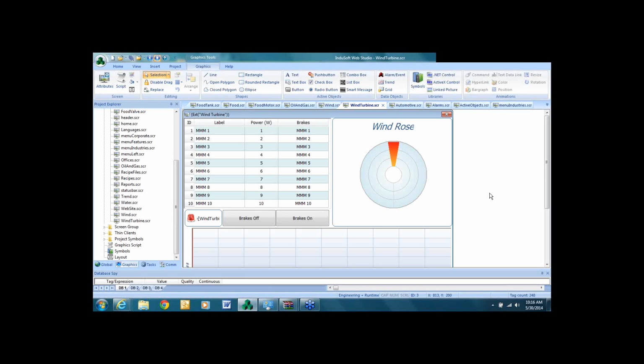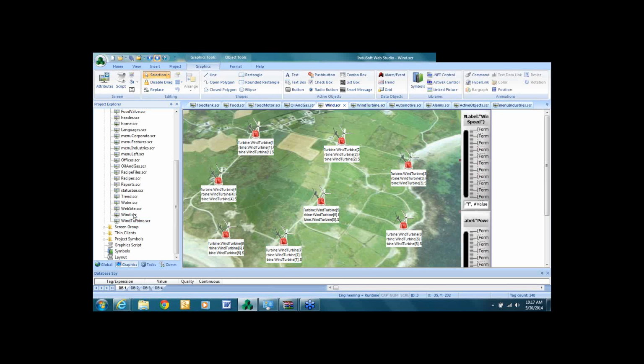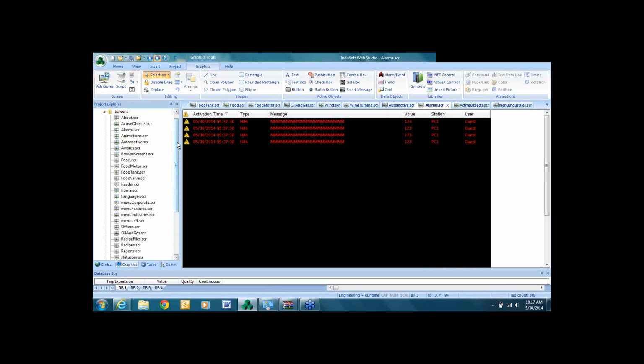Okay, the voice is still low, Con, so can you demonstrate the screens again? He was showing on one screen there was wind turbines where you can see the energy being generated by the wind turbines. And there was also red lights which could show and which could indicate either undesired conditions or if there's a problem with the wind turbine. So somebody could go out and check it. Through Indusoft SCADA software, email alarms could also get sent out to the proper personnel so they'd know exactly which turbine to go service. So you wouldn't need to have a person that just regularly goes and visits the turbines. They could just go visit the turbine as needed.